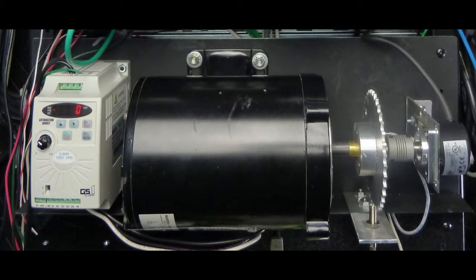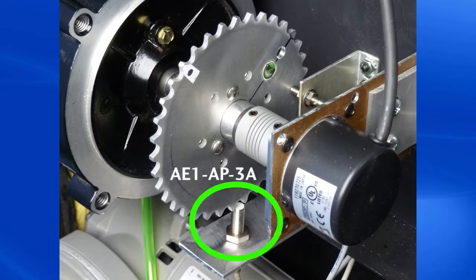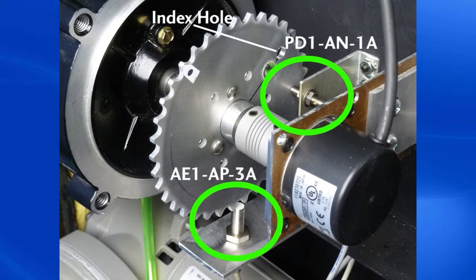Because the motor is independent, the Productivity 3000 has to rely on sensors fed into its HSI module for all of its information. In particular, we have this proximity sensor counting teeth on the sprocket and another proximity sensor detecting its index hole. Those are on channel 2 of the HSI card.